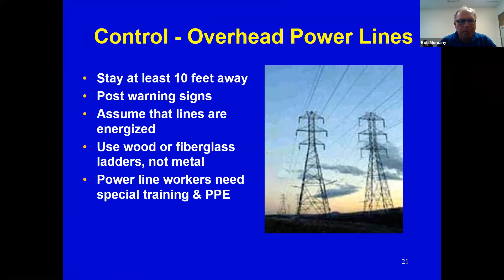And you always have to take into consideration their sway. You get some wind, lines can sway. Them in a lift or something like that, or scaffolding, can sway because of the weather conditions, and I could get within that 10 feet. Also, post warning signs reminding employees working under power lines that there are overhead power lines that are energized, to warn them not to work with anything elevated in that area. Make sure that any of your equipment is non-conductive equipment. And then they have proper personal protective equipment as well.